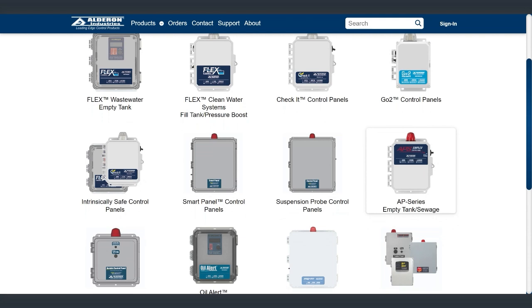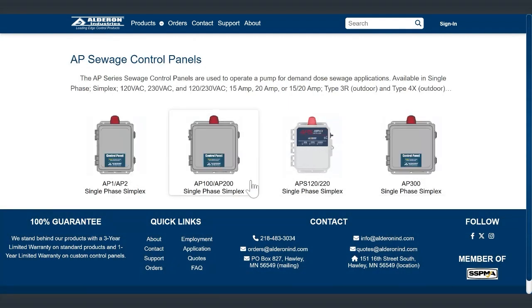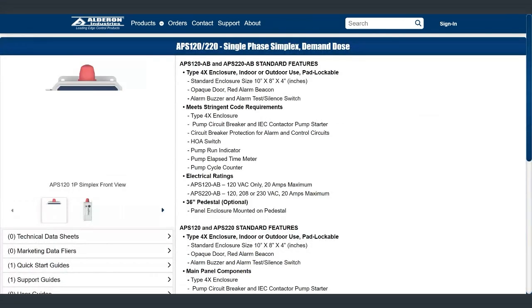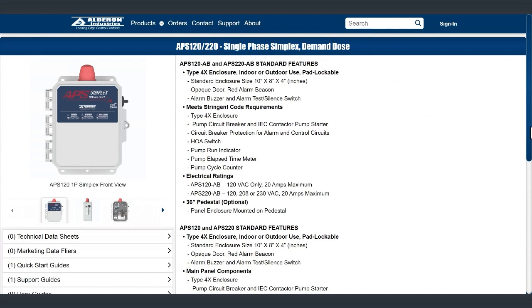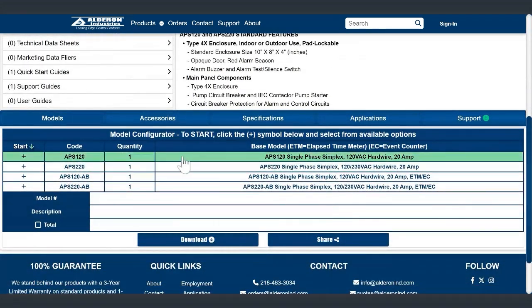Do you guys have anyone requiring a cycle count or any of that? On occasion. It's not like per jurisdiction or anything like that. No, we don't stock up with the timer or a counter. You do not. Not normally. If we go into that, there's some limited options for that. You can do 120 or 230, and then single phase, you can get it with the hardwired, with the elapsed time meter and the event counter, and these are all good up to 20 amps.